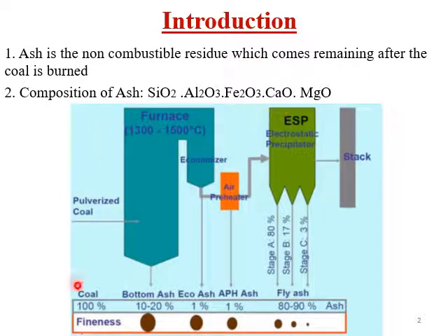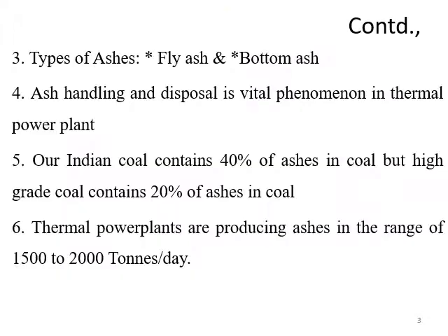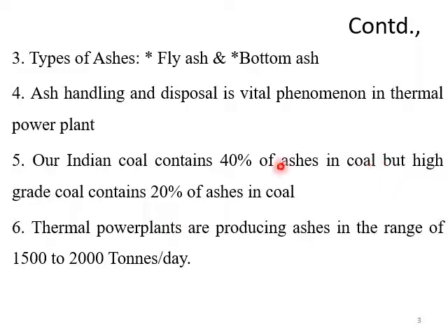This is an introduction. The types of ash are fly ash and bottom ash. Ash handling plays a challenging role in a thermal power plant. In Indian coal, there is about 60% ash content, which is very high. If you use high-grade imported coal, the ash content is low, meaning lower fuel consumption and lower ash generation.